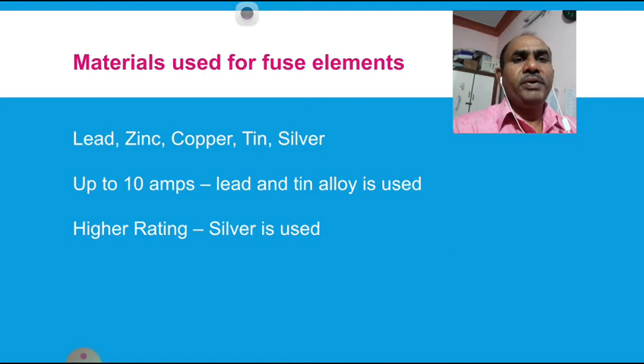Now, what are the materials generally used in fuses? Already we know that fuse materials are lead, zinc, copper, tin and silver. Up to 10 amperes we can use an alloy of lead and tin because it has a low melting point. For higher ratings we can use silver, and for time lag operation we can use zinc. These are some special types of fuses for different applications.